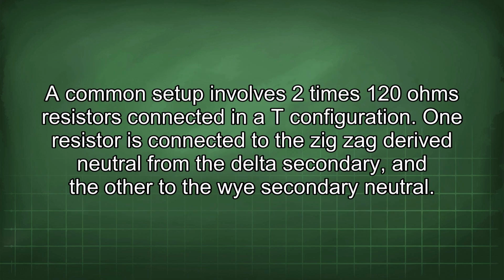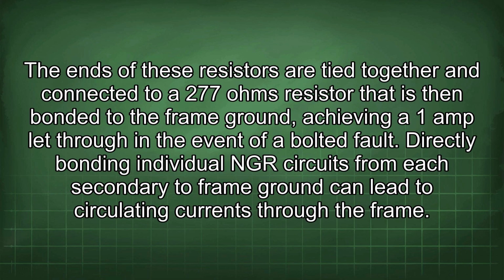A common setup involves 2 times 120 ohms resistors connected in a T configuration. One resistor is connected to the zigzag derived neutral from the delta secondary and the other to the Y secondary neutral. The ends of these resistors are tied together and connected to a 277 ohms resistor that is then bonded to the frame ground, achieving a 1 amp let-through in the event of a bolted fault.